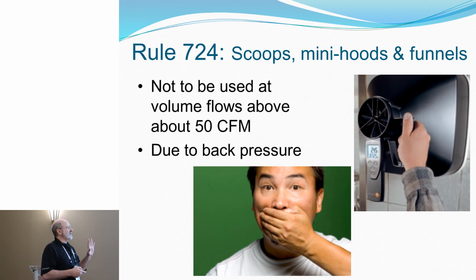Scoops, mini hoods, and flow funnels. You got to be careful about using those outside of their operating conditions. These are designed, I believe it's below 50 at this point, so you can use it for ideally exhaust flow below 50 CFM. That's what they're designed to be used for. There's actually, last couple years, they made a flow straightener, a tube with a grid in it to get rid of that swirl. It's a swirl killer, not a squirrel killer. High efficiency furnaces are squirrel killers. It's a swirl killer, so it deadens that swirl flow so that the device doesn't get impacted by that. So that's an adaptation to that product. But smothering the outlet, the back pressure can cause the system effect and things to talk back.